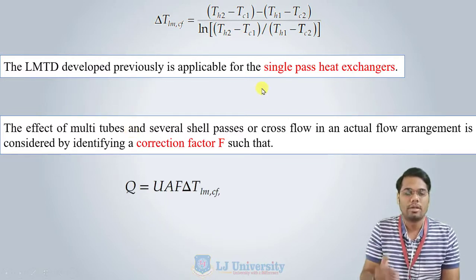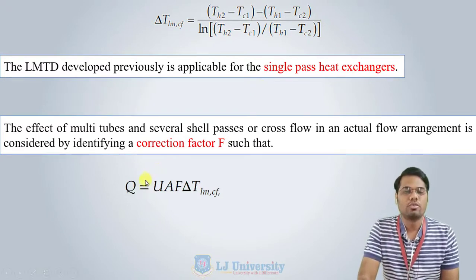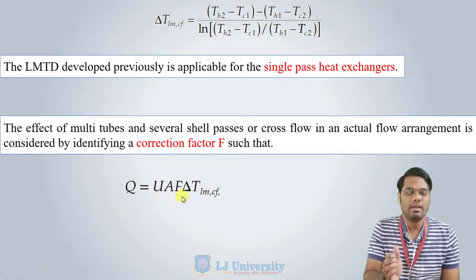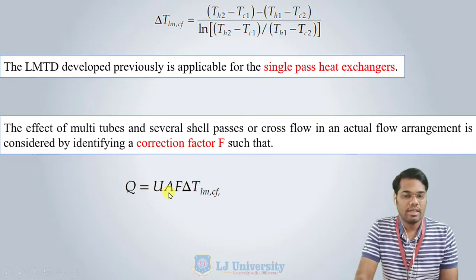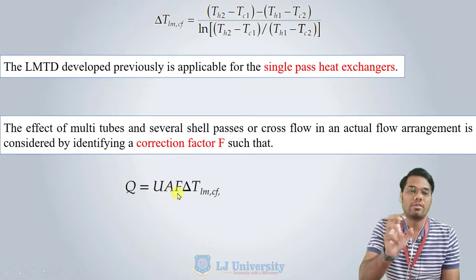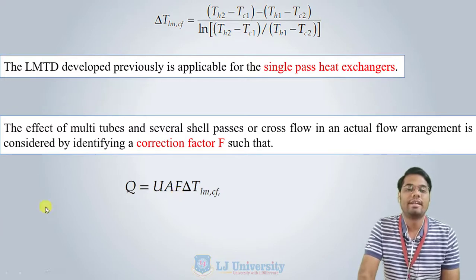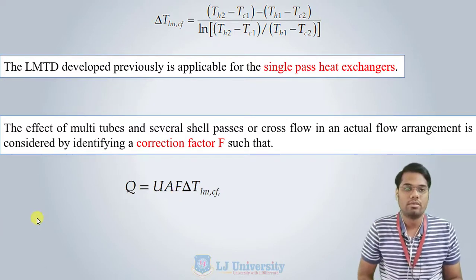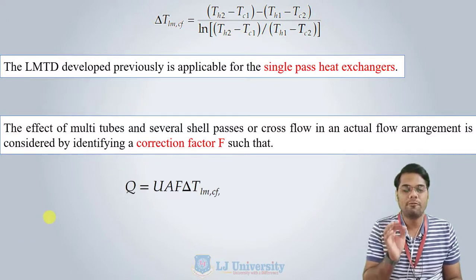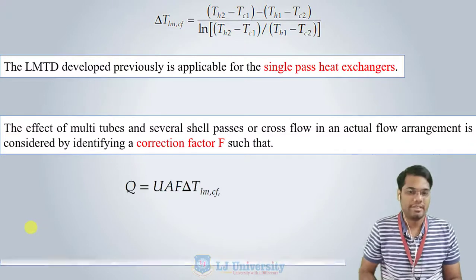Our equation for multi-tube, multi-shell-pass heat exchangers becomes Q = U·A·F·ΔT, where U is the overall heat transfer coefficient, A is the area, F is the correction factor required for the multipass or shell-and-tube heat exchanger, and ΔT is the mean effective temperature difference of the whole heat exchanger.